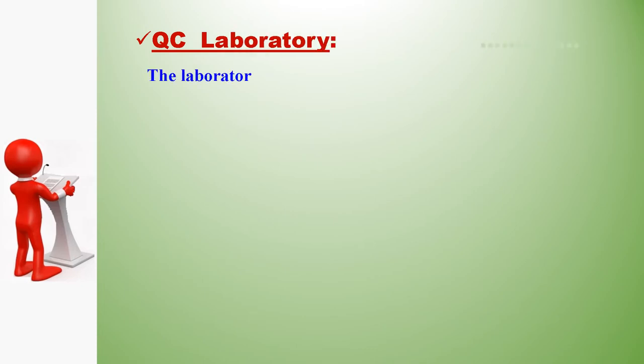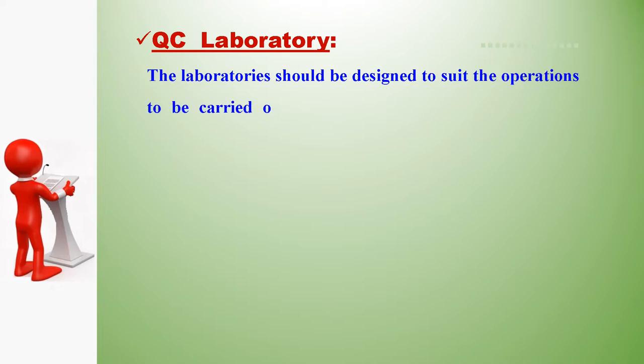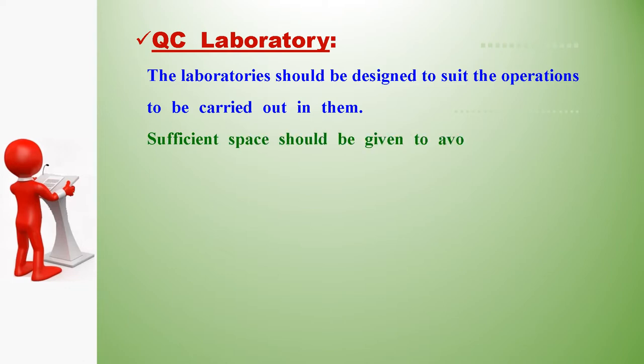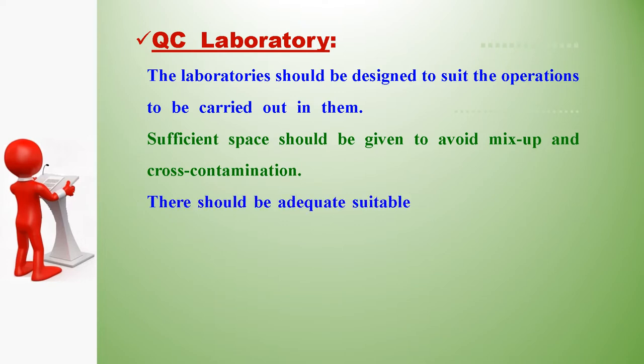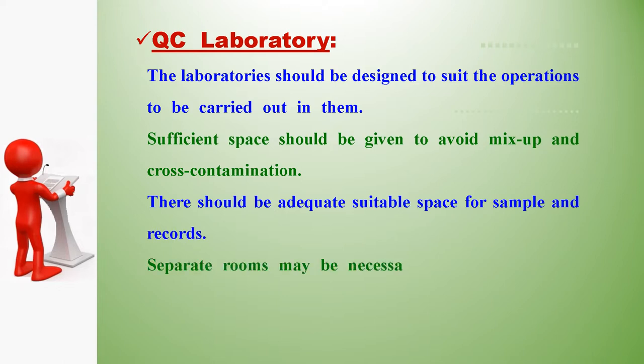The QC laboratories should be designed to suit the operations carried out in them. Sufficient space should be given to avoid mix-up and cross-contamination. There should be adequate and suitable space for samples and records. Separate rooms may be necessary to protect sensitive instruments from vibration, electrical interference, humidity, and similar conditions.